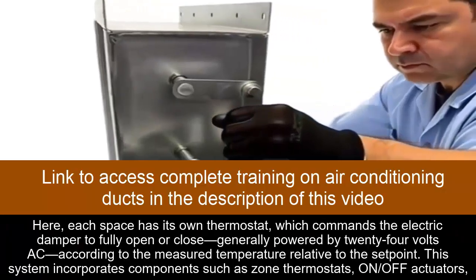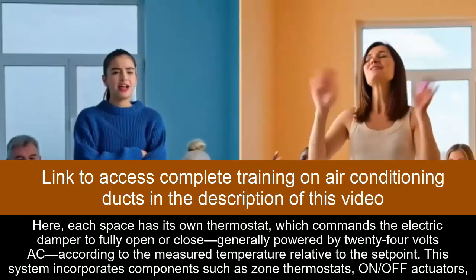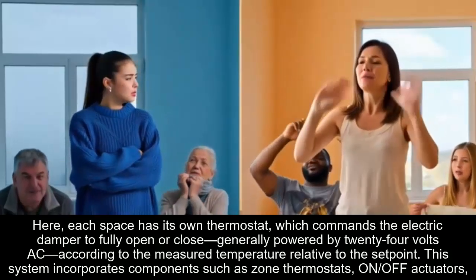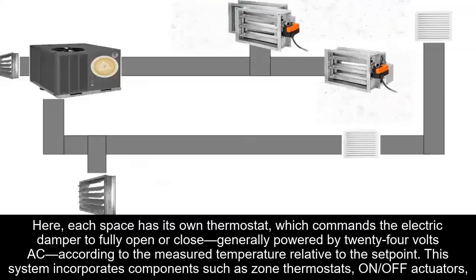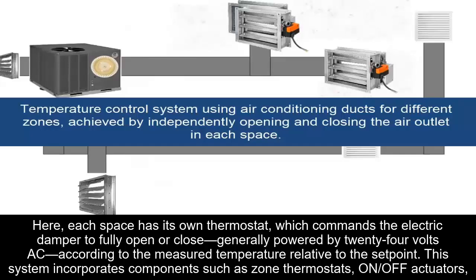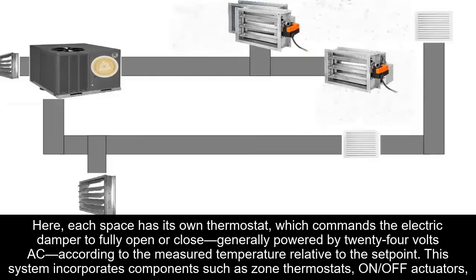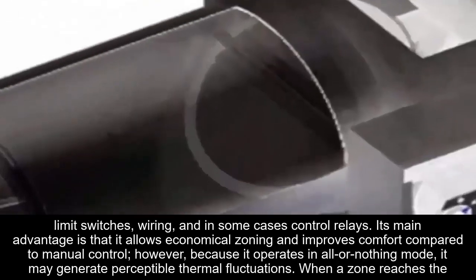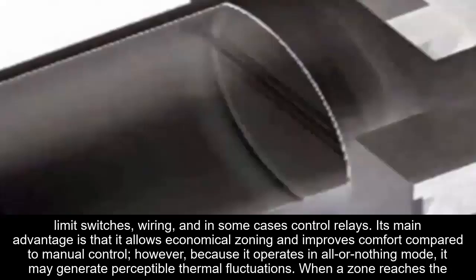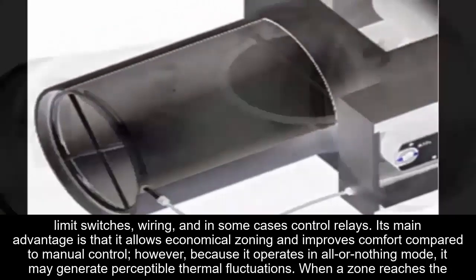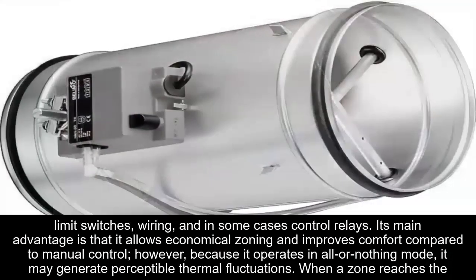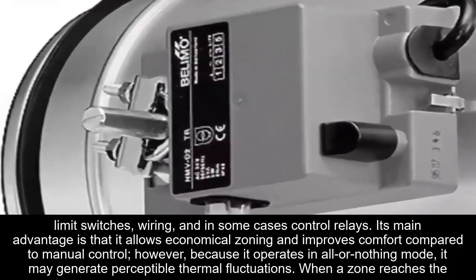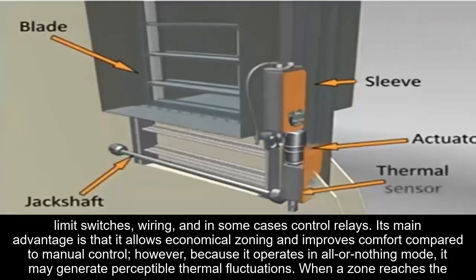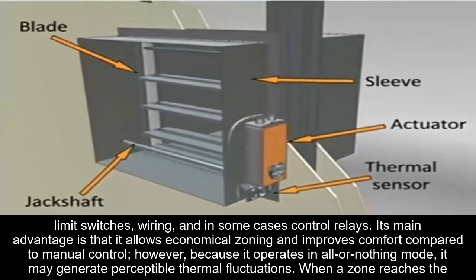Here, each space has its own thermostat, which commands the electric damper to fully open or close, generally powered by 24 volts AC, according to the measured temperature relative to the set point. This system incorporates components such as zone thermostats, on-off actuators, limit switches, wiring, and in some cases control relays. Its main advantage is that it allows economical zoning and improves comfort compared to manual control. However, because it operates in all-or-nothing mode, it may generate perceptible thermal fluctuations.